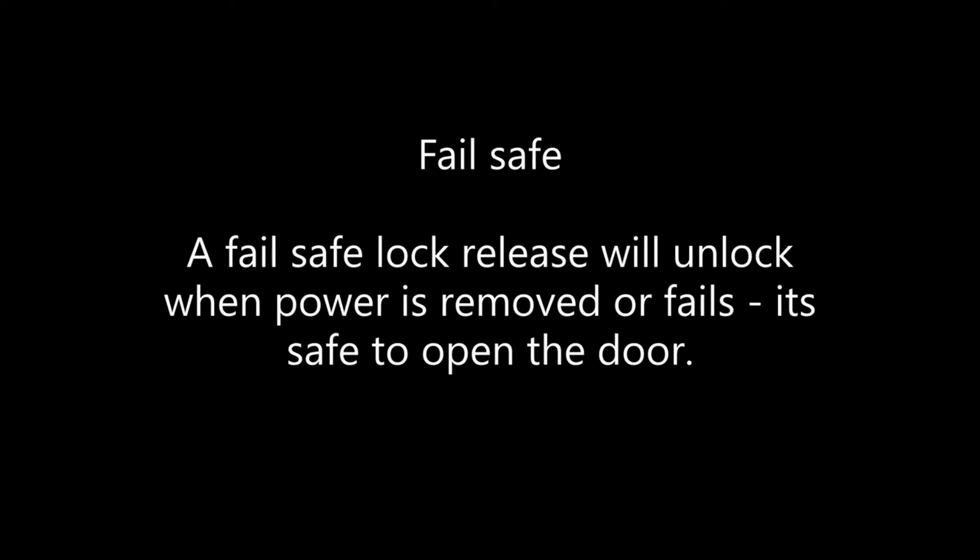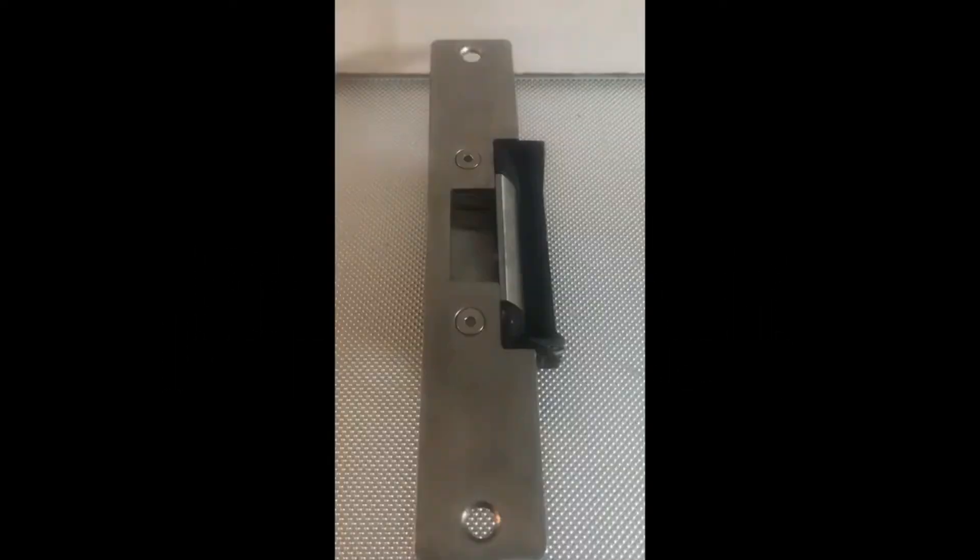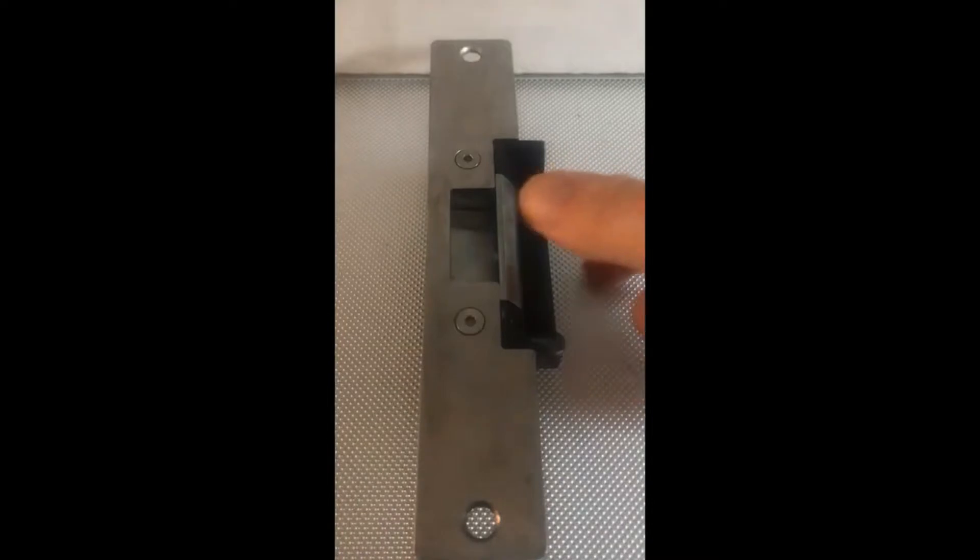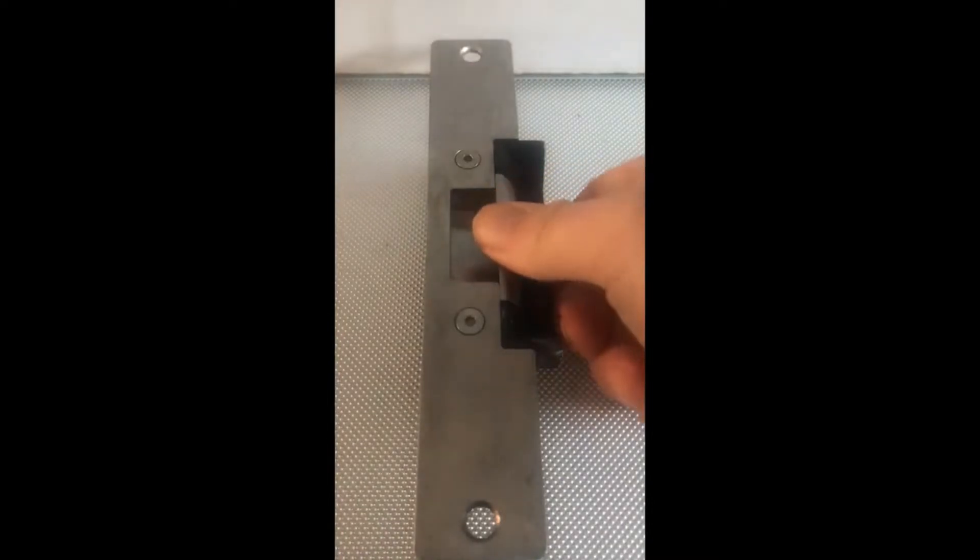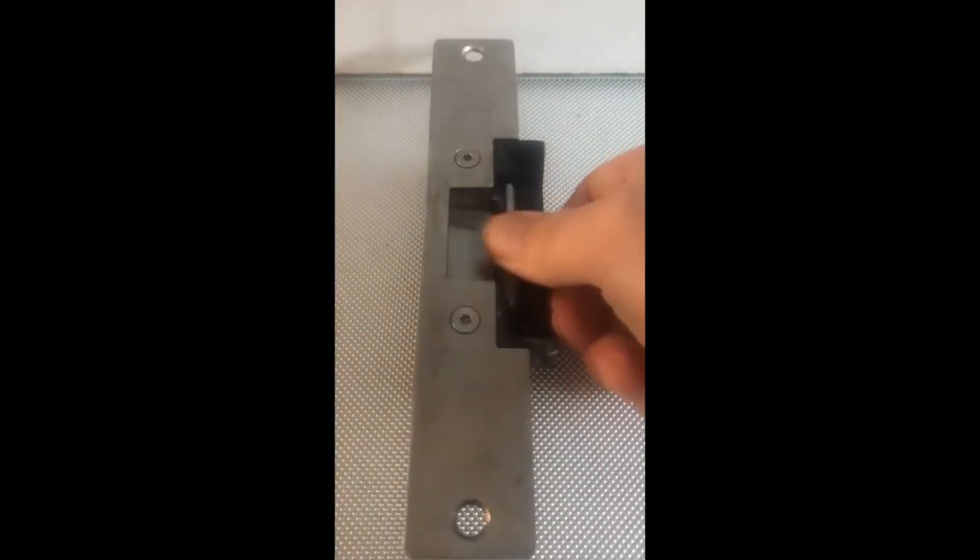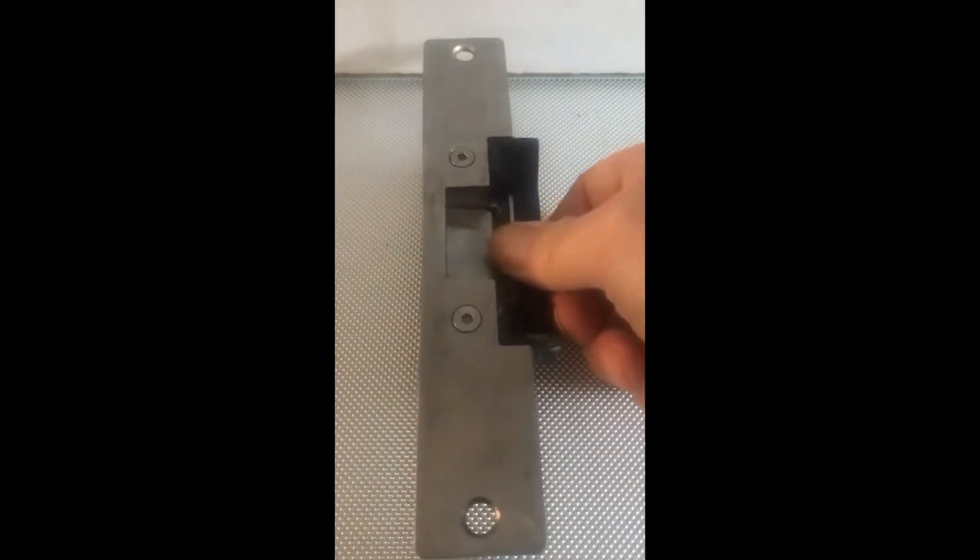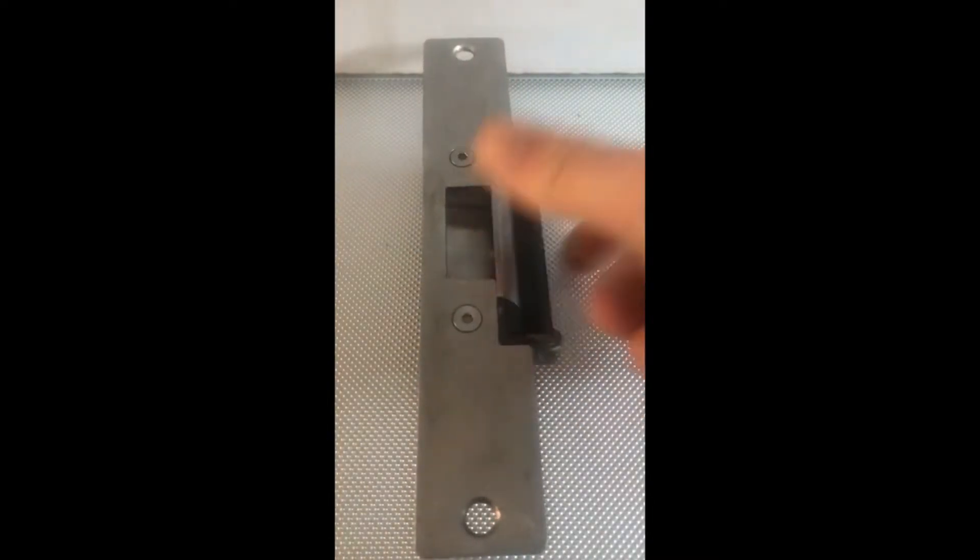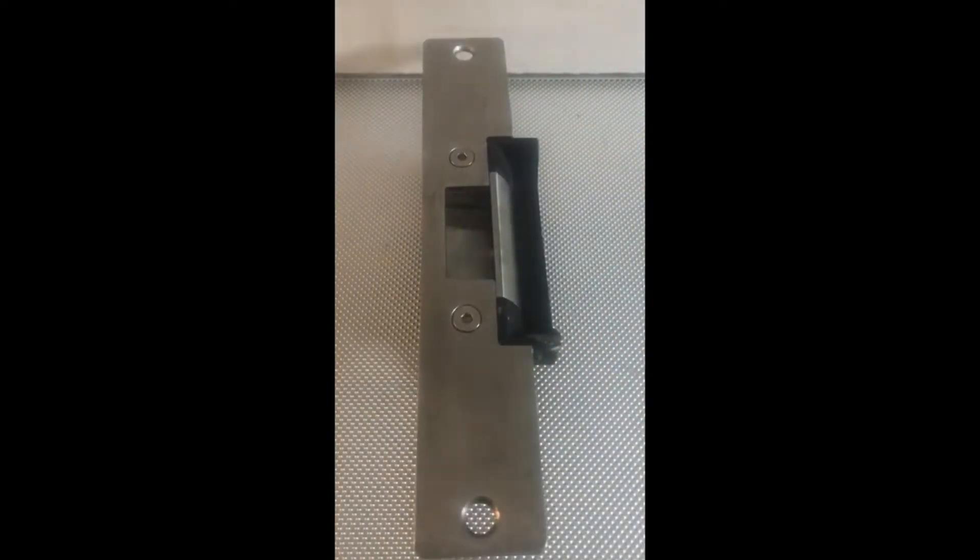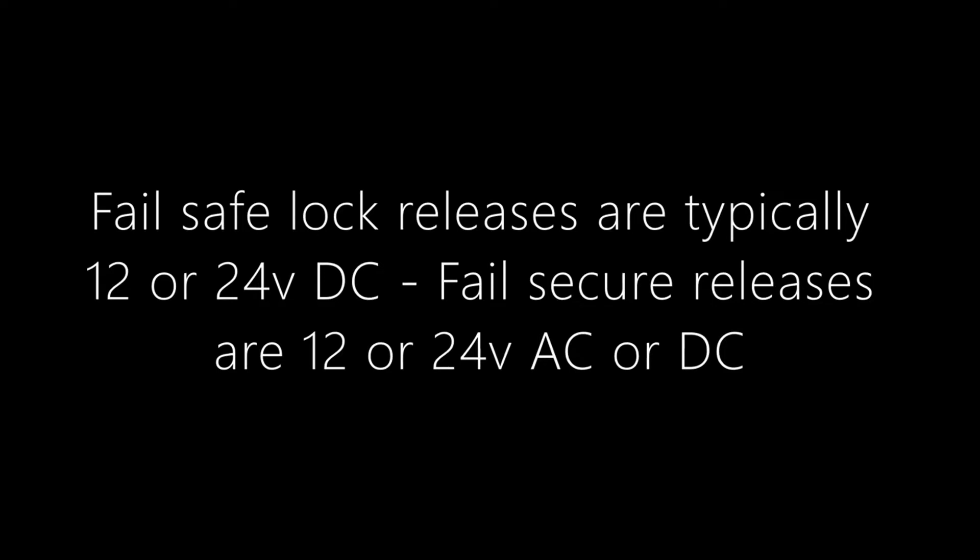Failsafe. A failsafe lock release will unlock when the power is removed or fails, making it safe to open the door or escape. With no power, the release is free to open. Failsafe lock releases are typically 12 or 24 volts DC. Failsecure releases are 12 or 24 volts AC or DC.